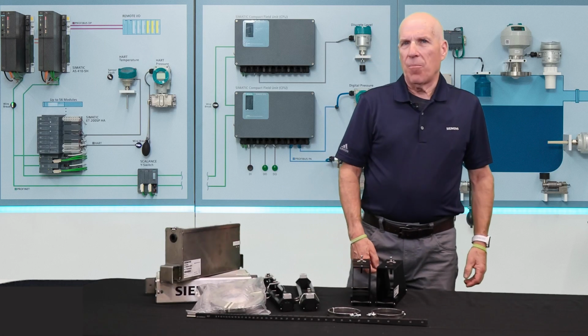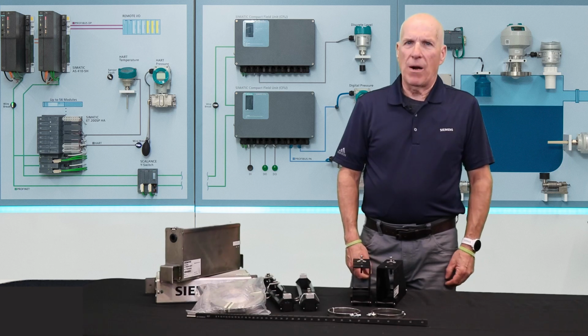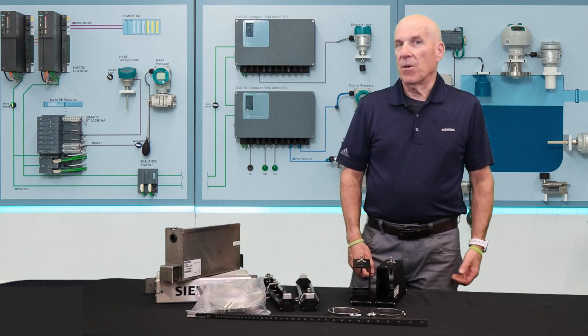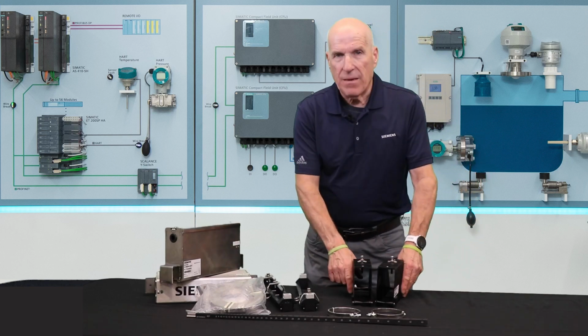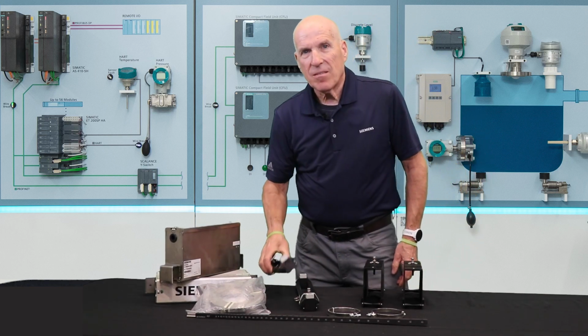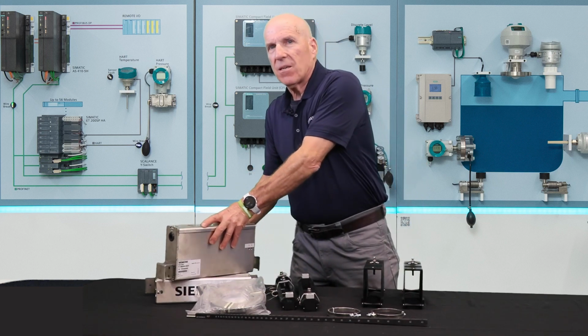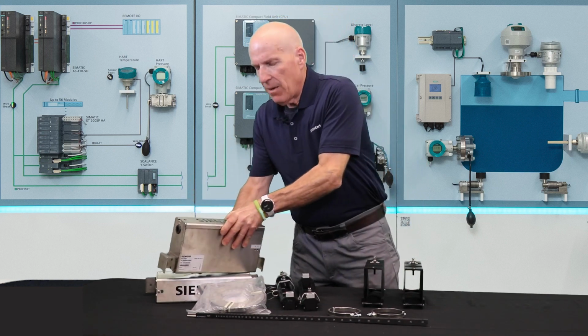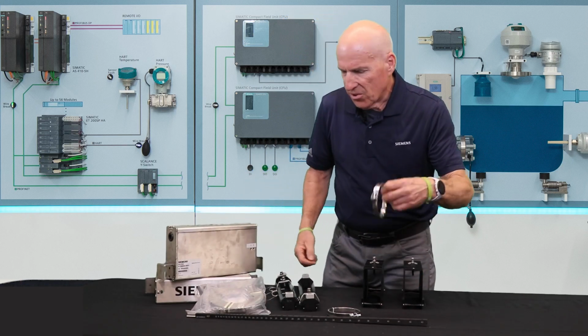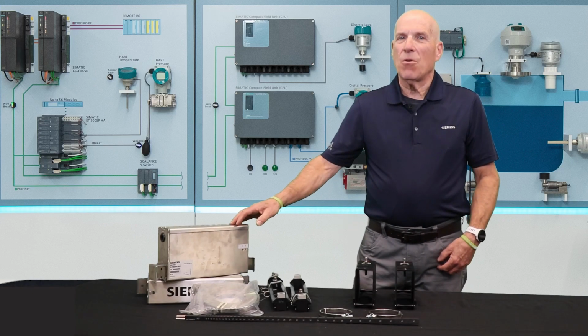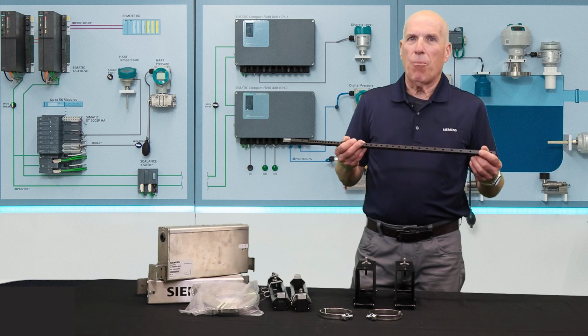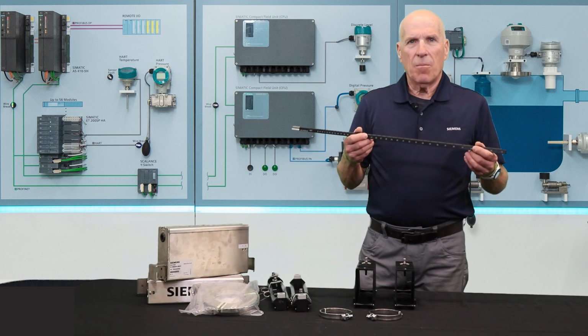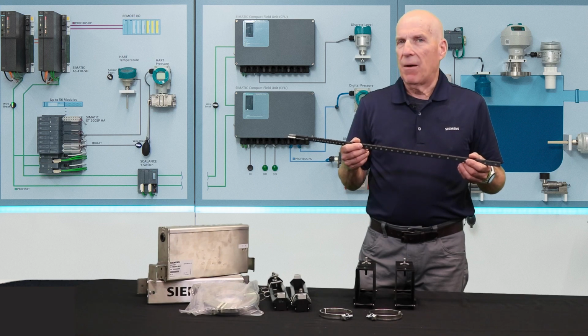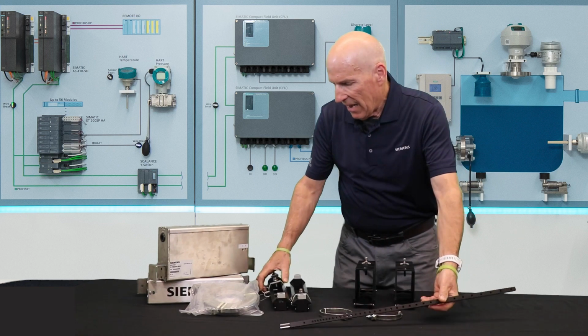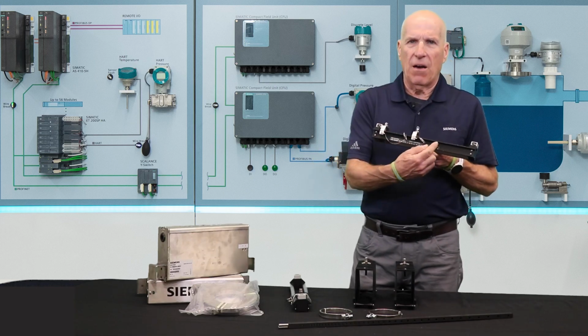To install your sensors on the pipe, you'll receive appropriate mounting hardware, also identified on the system label. These can take the form of mounting frames, mounting tracks, or robust stainless steel enclosures. They are attached to the pipe using the supplied stainless steel straps, depending upon the type you get. Both the frames and the stainless steel enclosures use a spacer bar to set the appropriate distance between the flow sensors. The bars come in different lengths depending upon the pipe diameter specified. Tracks have integral mounting positions identified on the side of the rail.